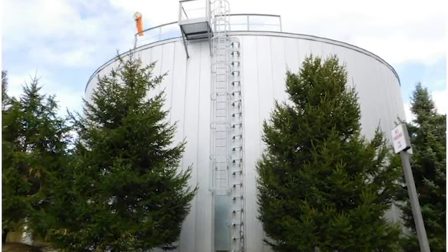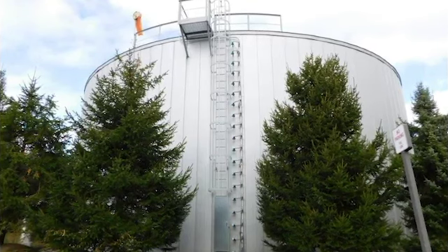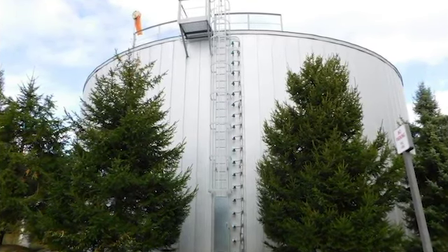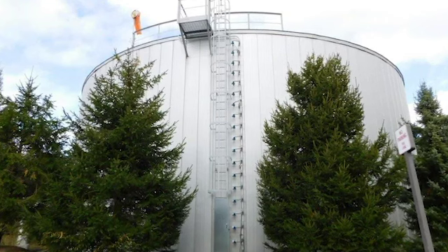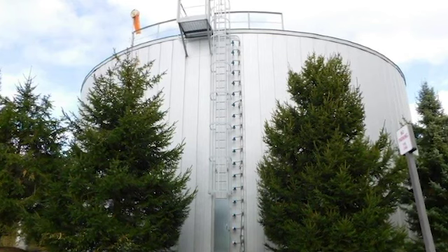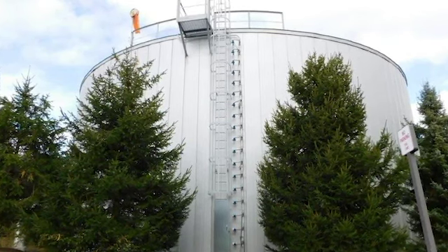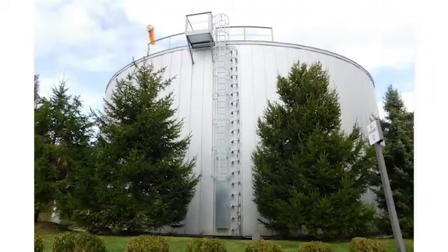The tank itself is a really simple design. It has spiders on the top and on the bottom of the tank. It works on a thermocline principle, where at the top, the water temperature could be 58, 59 degrees Fahrenheit, and at the bottom, it could be 39, 40 degrees Fahrenheit. And there's about a 1 foot band of 2 temperature waters at different densities. And of course, the colder water, being more dense, sinks to the bottom. We lay it into the tank very gently using those spiders, and that prevents the tank from getting mixed. So the whole tank works on a thermocline density principle, and it works extremely well. And it's just chilled water, just water with a little bit of corrosion inhibitor and biocide in it to keep the system clean.